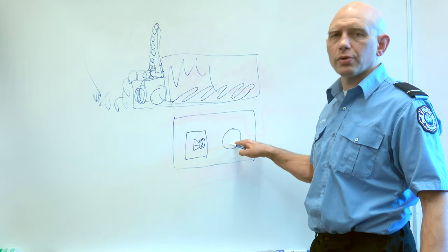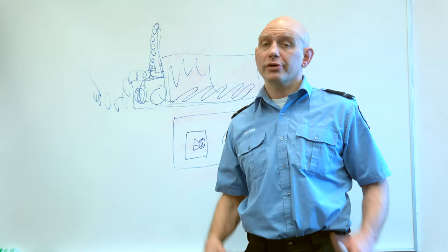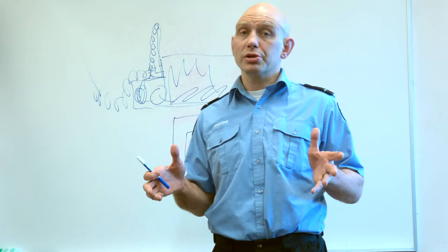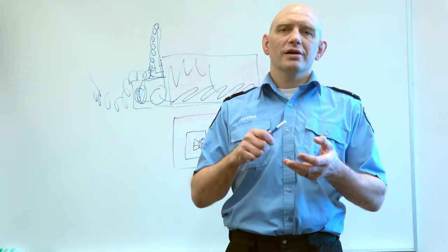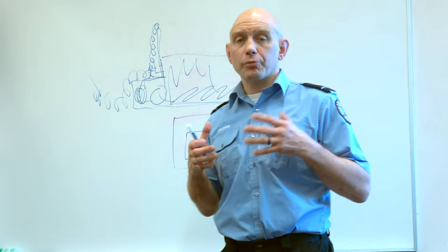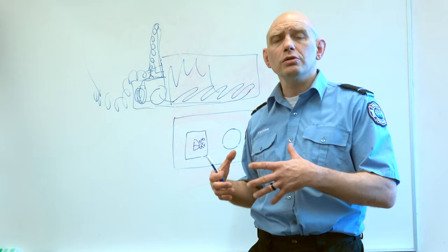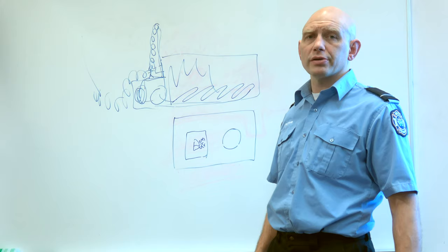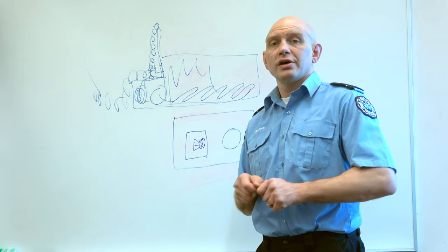If there's fire impinging on the ammonia room and the ammonia room's leaking, or even if it's not, that's an additional source of fuel for the fire. It's a potential bomb if you get to the right concentration between the LEL and the UEL and it blows up. So it's important to note that this operation, opening that emergency release valve, is like your last ditch, everything else has failed maneuver. You're going to have to do it in coordination with evacuating people downwind, plume modeling, trying to figure out where that ammonia is going to go. The other thing that's in those boxes sometimes, there'll be a valve here, sometimes there's an electrical switch here. That electrical switch is the power to the compressors in the ammonia room.